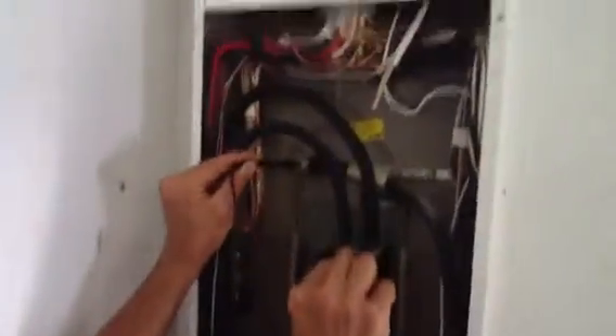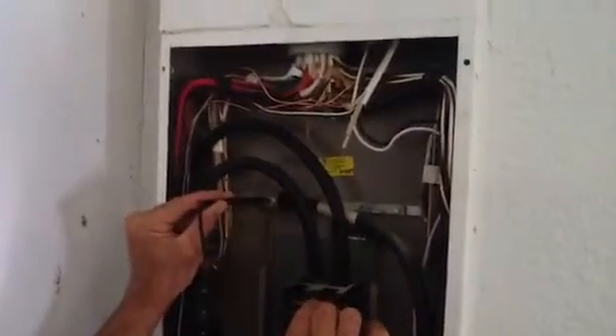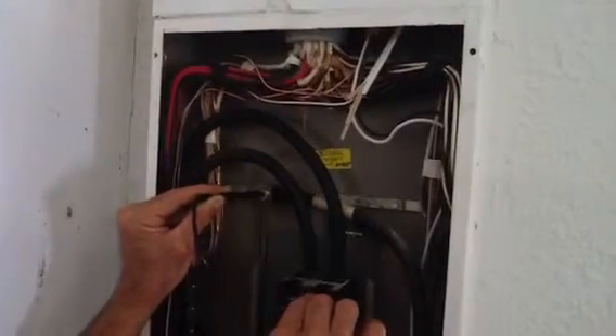Now look at the meter. You'll see 241.4 volts. Now we know we have 240 volts. Now let's just make sure each leg is working. So I'm going to go from each leg. I'm going to put one probe on the neutral up here, and one probe on the breaker. Okay, now you've got 120 volts on that leg. Now what I'm going to do is I'm going to move the probe out, and I'm going to put it on the other side of the breaker. And I have 120 volts.